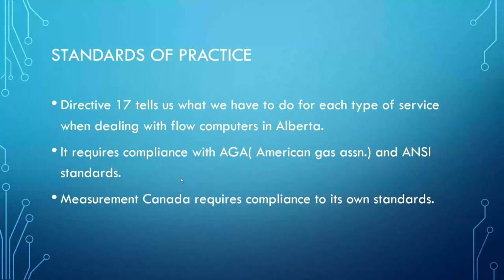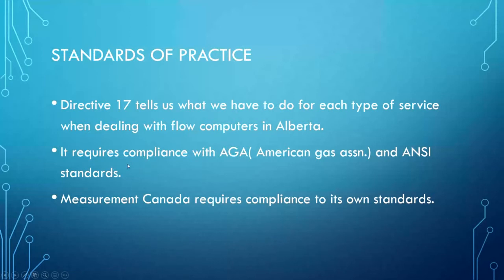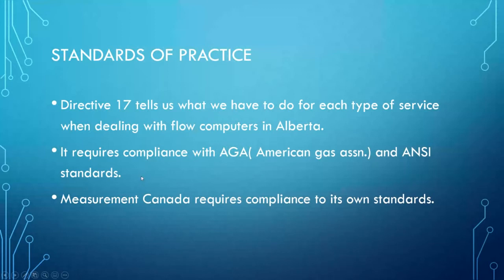There are standards of practice associated with flow computers. In Alberta, Directive 17 tells us what we have to do with each type of service, requiring compliance with American Gas Association and ANSI standards. Different AGA numbers relate to different measuring devices. Measurement Canada also requires compliance to its own standards. This is essentially an accounting situation — we want to make sure apples are compared to apples and oranges to oranges.